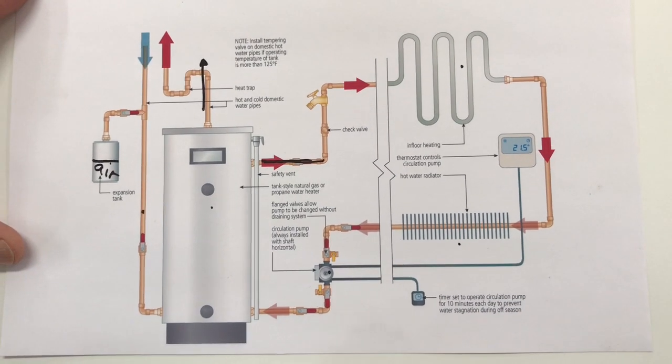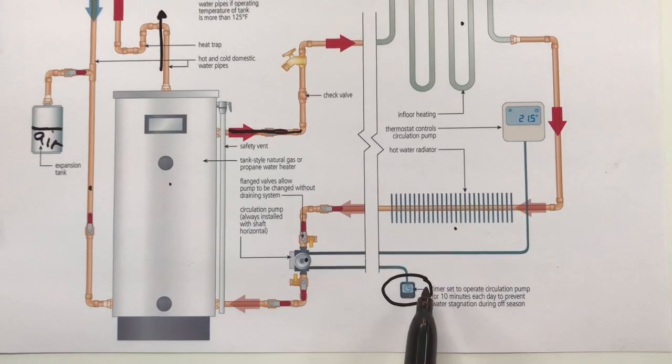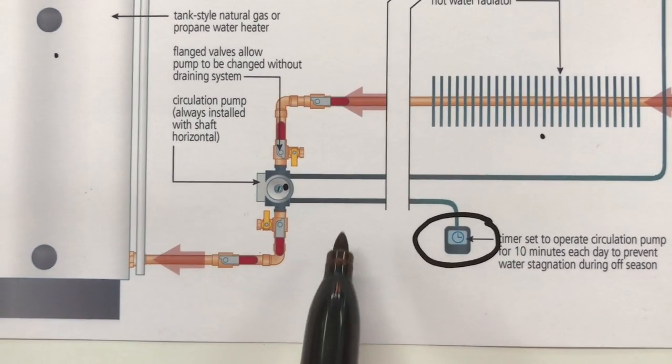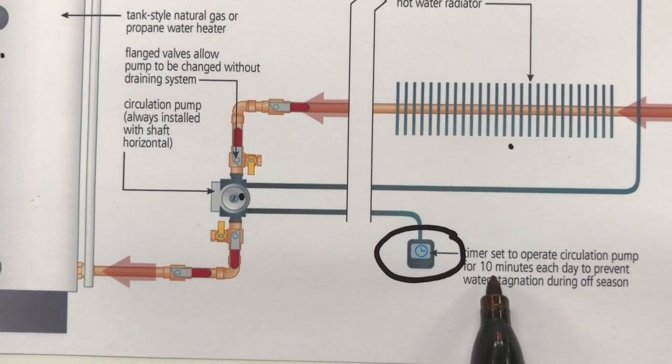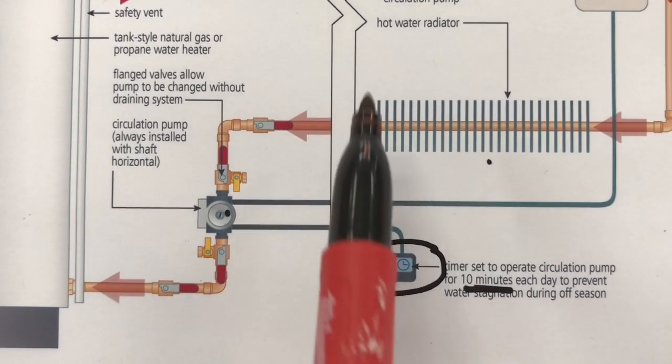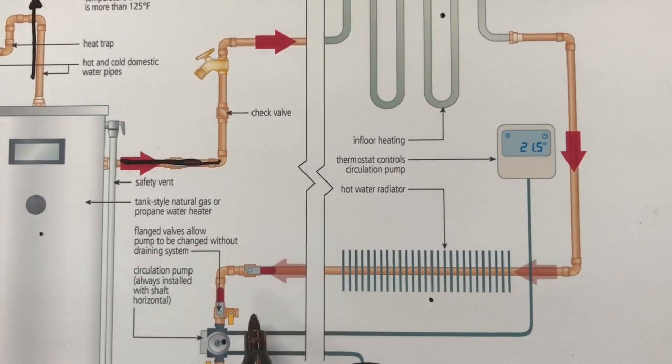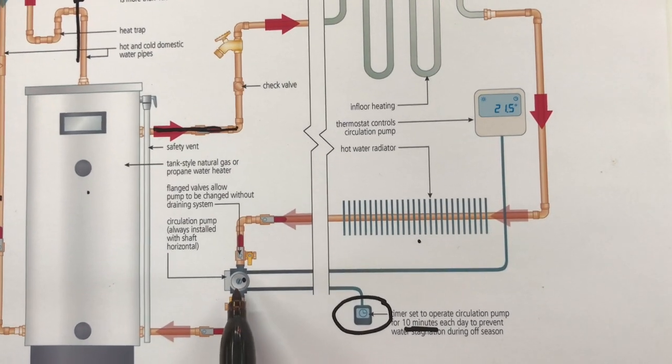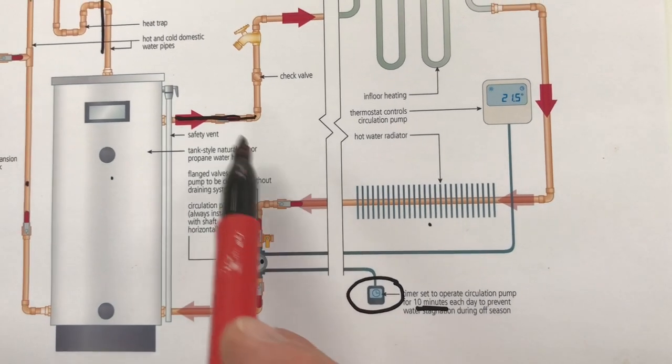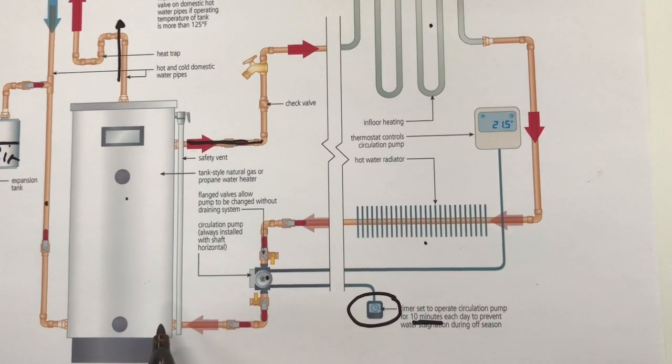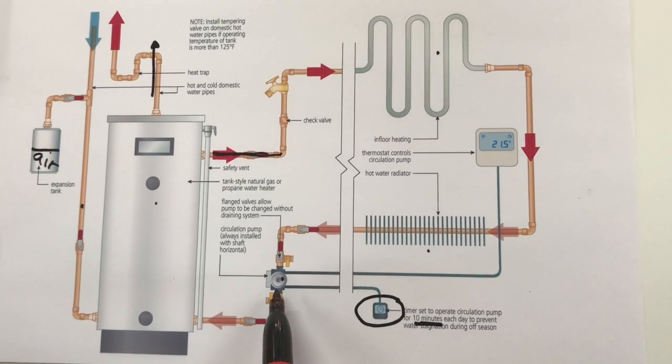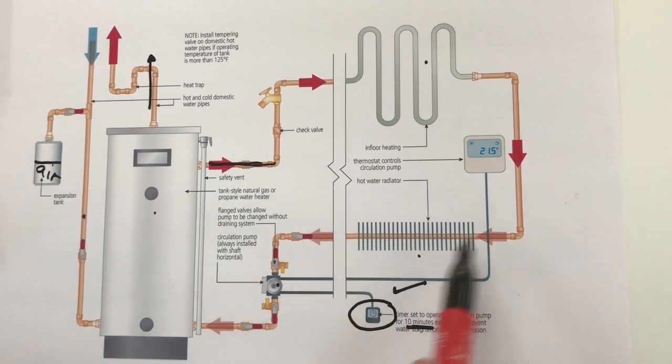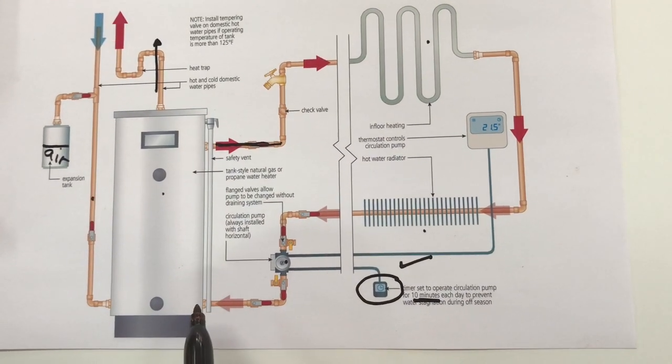One way around the stagnation problem is to wire in a timer like you see here. Now this will activate the circulator pump whether heat is called for or not for about 10 minutes each day. And that serves to move the water through the hydronic system long before it would ever get stagnant. It's actually good for the pump for it to run regularly like that even in the off season. And some jurisdictions will say yes that's okay.